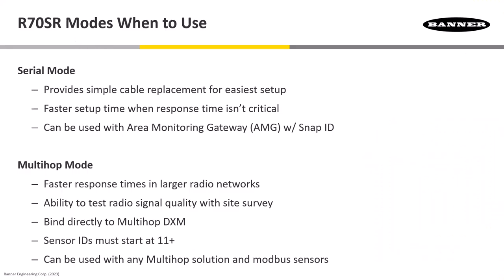The two different modes available on the R70SR are Serial Mode and Multi-Hop Mode. Serial Mode provides a nice, simple cable replacement with very easy setup to go between serial radios. It does have a much faster setup time. However, when you add more and more of these R70 radios on, response time can slow down. So in cases where response time isn't critical, larger networks in serial mode are completely fine.